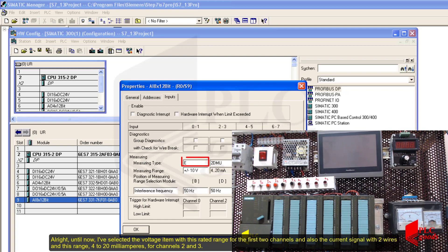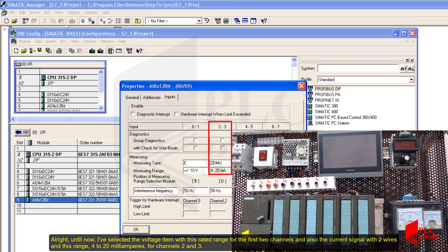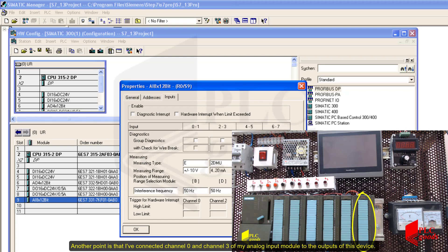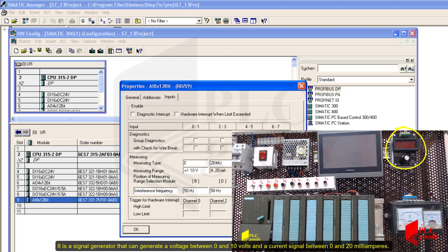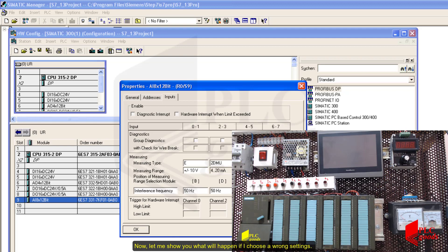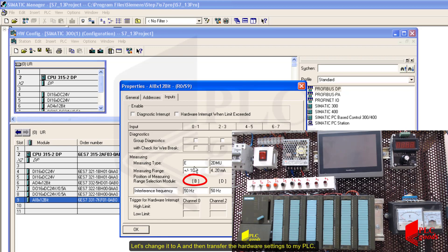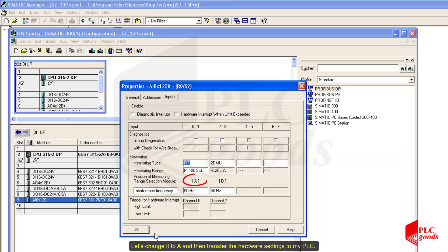Until now I've selected the voltage option with the +/-10 V rated range for the first two channels, and the current signal with two wires at 4–20 milliamps for channels 2 and 3. I've connected channel 0 and channel 3 of my analog input module to the outputs of a signal generator that can generate a voltage between 0 and 10 volts and a current signal between 0 and 20 milliamps. Now let me show you what happens if I choose the wrong settings — I'll change option B to A on the analog module and transfer the hardware settings to my PLC.